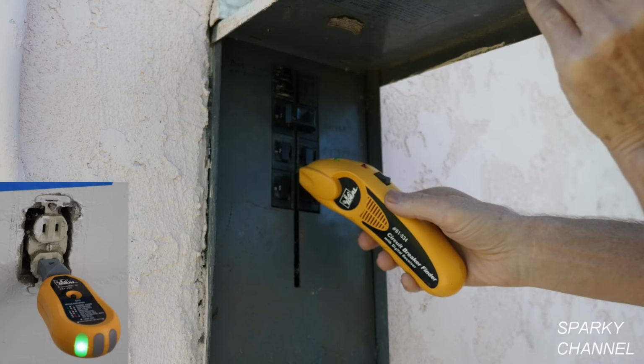See, I'm testing at 15 amps. Now, I could change it to 20 amps where you get 6.5% drop, and I could change it to 12 amps where you get 3.9% drop. Well, let's put it on 15. This is a maximum load. This is a 15 amp circuit. So this would be like a Skilsaw. This would be like using a Skilsaw on this receptacle. So this is a heavy load for this circuit.